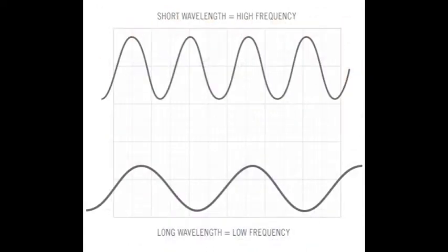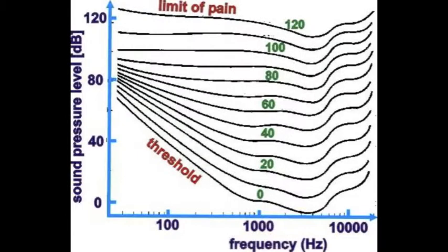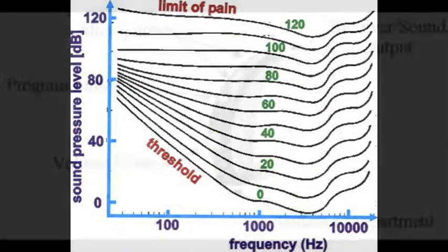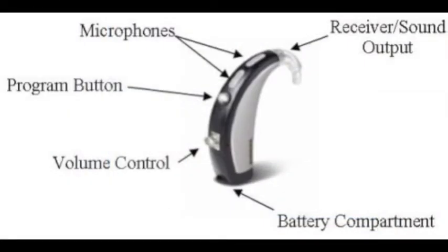How a hearing aid works. Hearing aids amplify sound based off of 2 components: pitch or frequency of the sound, and loudness or intensity of the sound source. They all have a power source or a battery. A hearing aid contains 1 or more microphones to pick up the sound, an amplifier that amplifies and processes the sound, and a receiver that sends the signal from the amplifier into the ear. An important thing you must remember is environment matters.